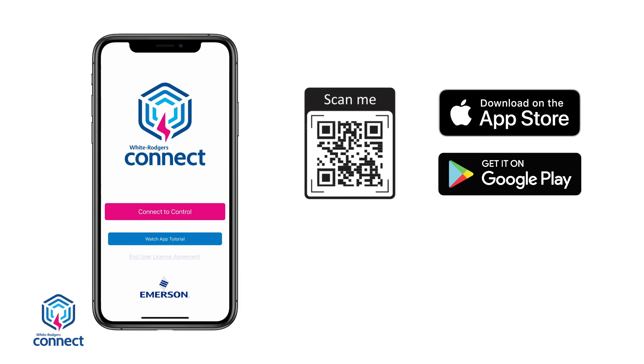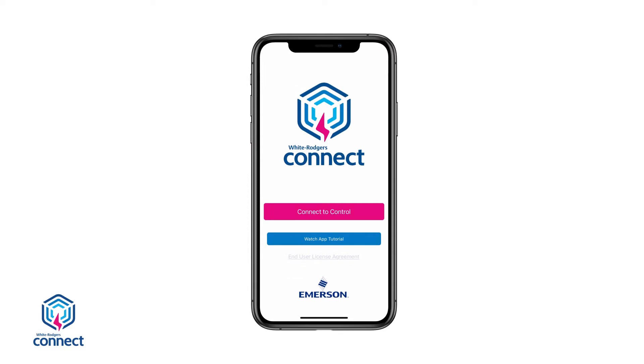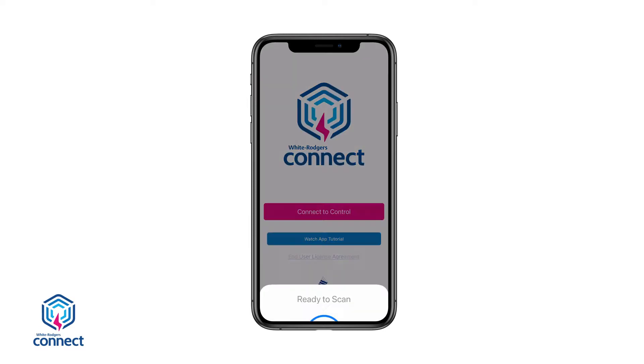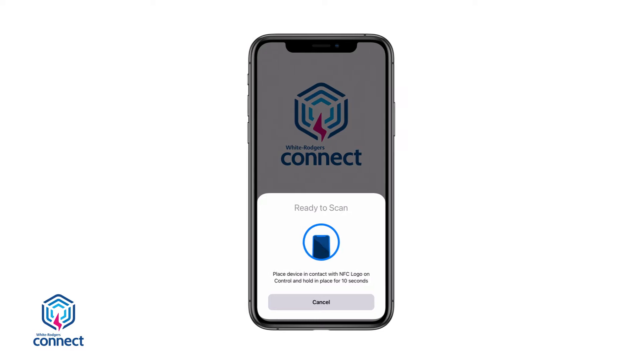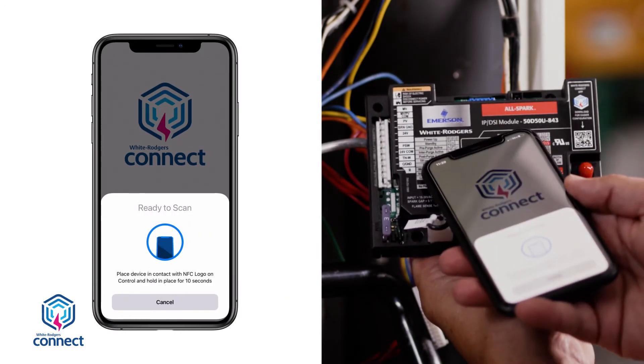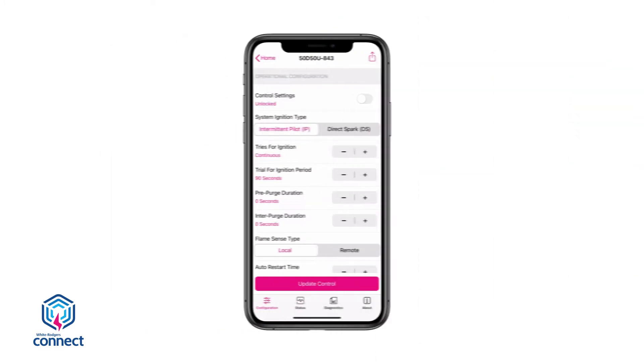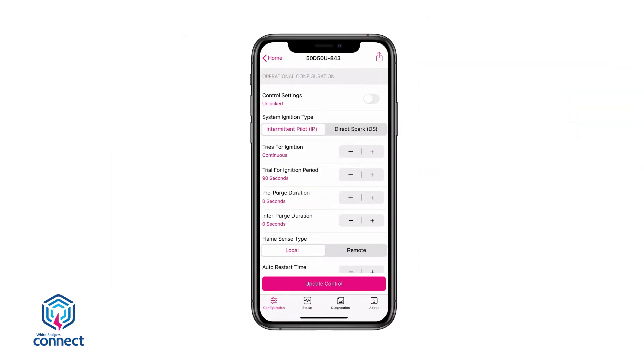To configure using the mobile app method, go to your mobile device's app store, search for White-Rodgers Connect, and download the app. Once downloaded, open the app. The home page has a Connect to Control button and a Watch Tutorial Video button. Select the Connect to Control button. The screen will show Ready to Scan. Place the mobile device in contact with the NFC logo on the module. A checkmark will appear showing the connection was successful.